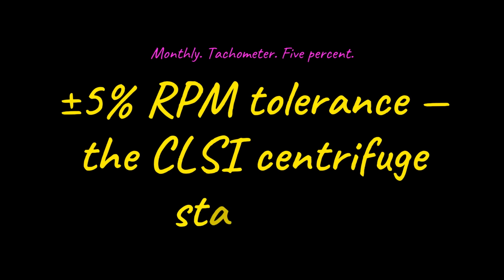Remember, centrifuge speed verification is performed monthly using an external tachometer, and the CLSI acceptable tolerance between displayed and measured RPM is plus or minus 5%. This single number controls the accuracy of every relative centrifugal force applied during routine specimen processing.